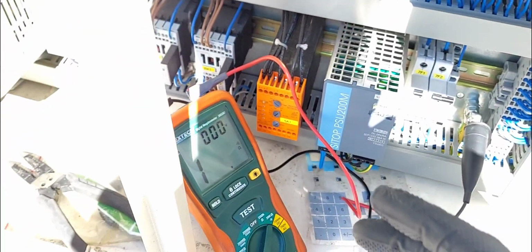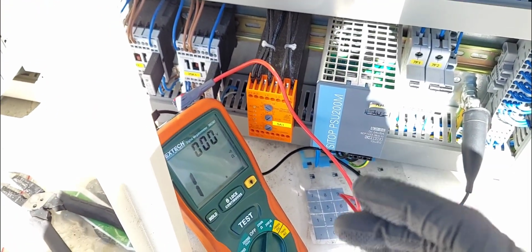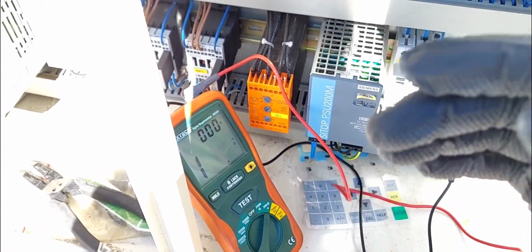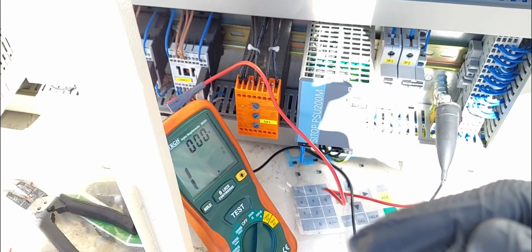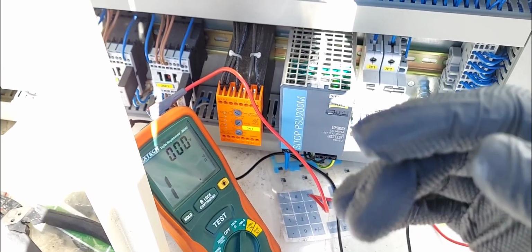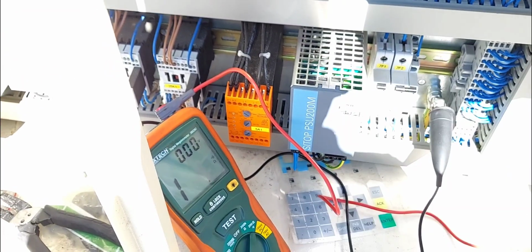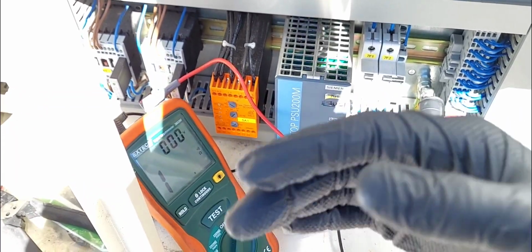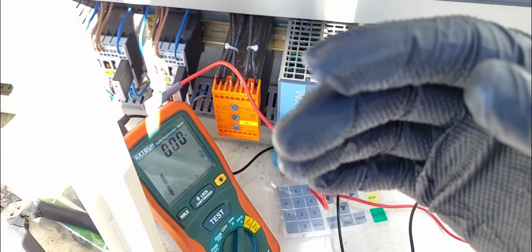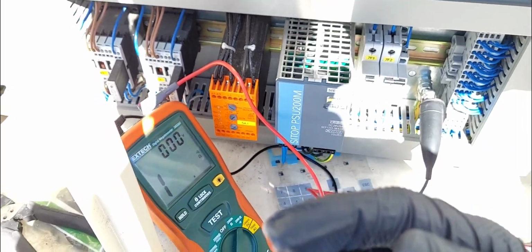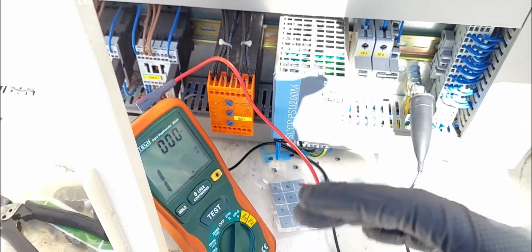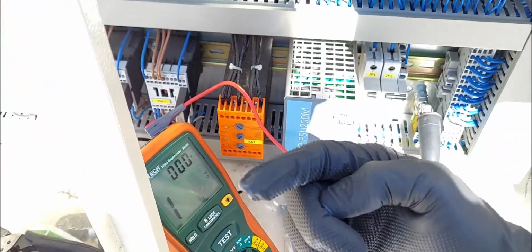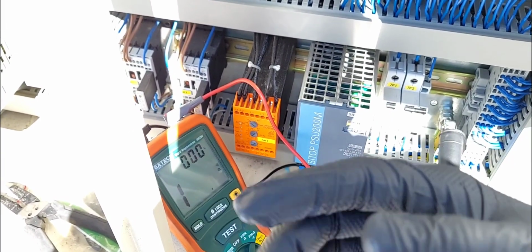When you're Meg testing your compressor winding, you're actually testing the resistance of the actual winding in the compressor between the grounding of the unit or the casing of the compressor. The case of the compressor is always going to be grounded to the chassis ground or the copper pipes. It's all metal, it's all connected. So inside you have the windings that make up the compressor windings.